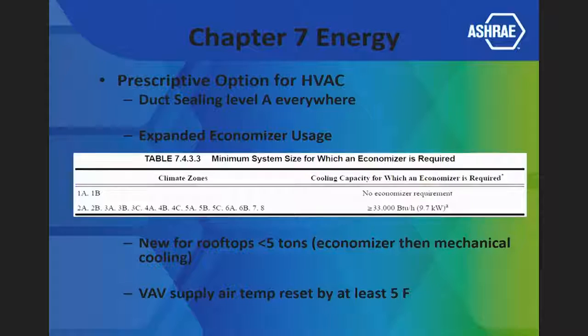If the air comes out at that temperature, then to regulate the temperature in the space, I'll just vary how much air I bleed into the space based on a thermostat. And so the damper regulates how much air I need. But nothing ever back at the unit changes the temperature of the air. So I've got to spend all that energy back at the unit. This says, hey, at certain times of the year, you don't need that cold of air.